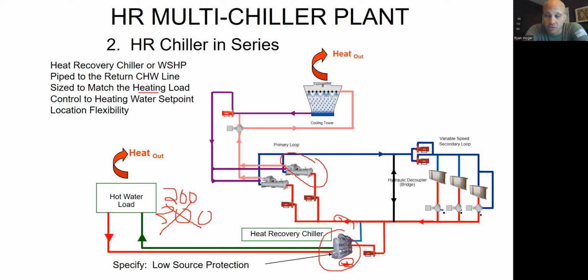If you've ever done a water source heat pump job, these are typically downtown high-rise type buildings. Each tenant will have a water source heat pump in the closet, which means they have a machine that takes water in, and it has a refrigeration cycle in it with a compressor and everything, and it makes warm or cold water, a little heat pump in there. And instead of dumping its heat to the outdoors like a residential heat pump, it dumps its heat into a water loop, and that water loop goes around the whole building.